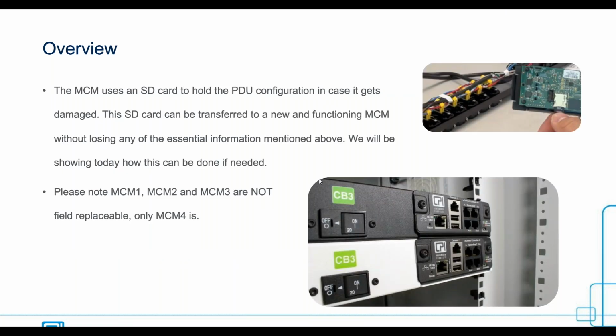So where does the MCM save all of this information? The main controller module uses an SD card to hold the PDU's configuration in the event of a failure or if it gets damaged. The good news is that the information in the SD card can be transferred to a new controller module when replaced properly without losing any essential information. Another important fact is that there are different types of MCMs depending on how old the PDU is.